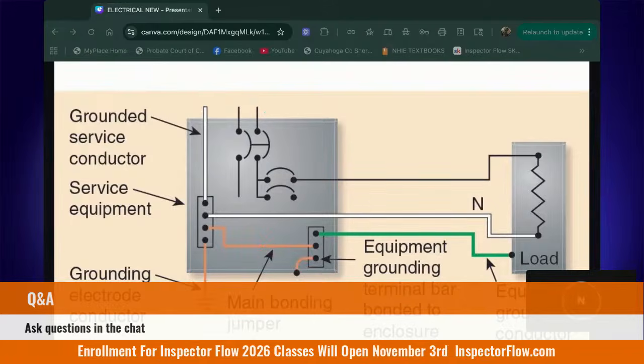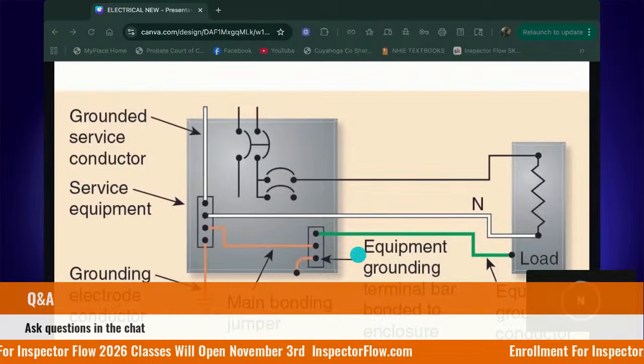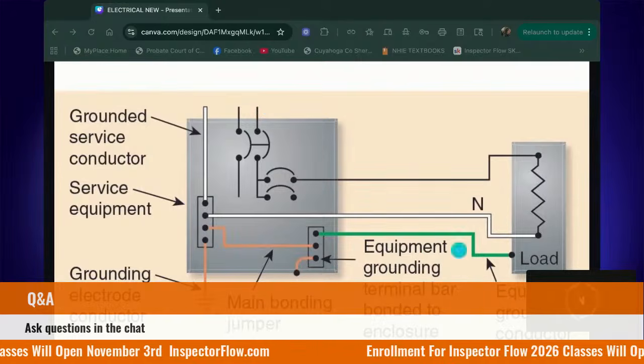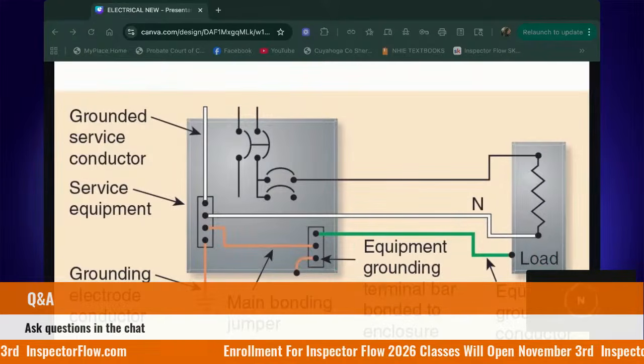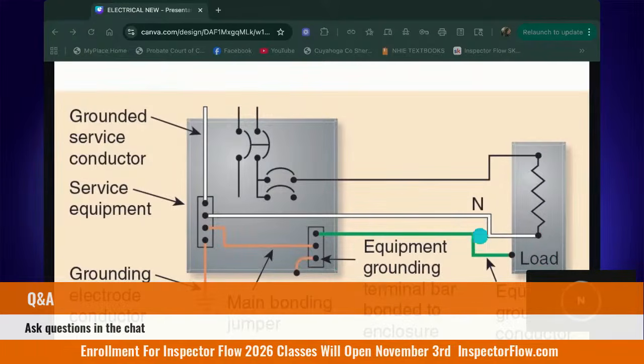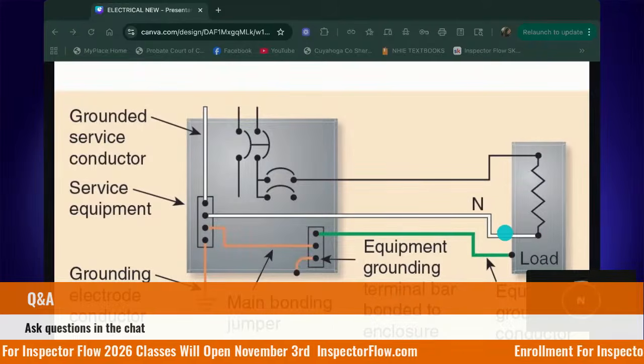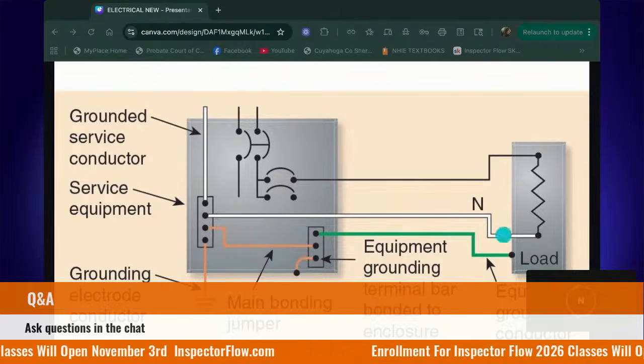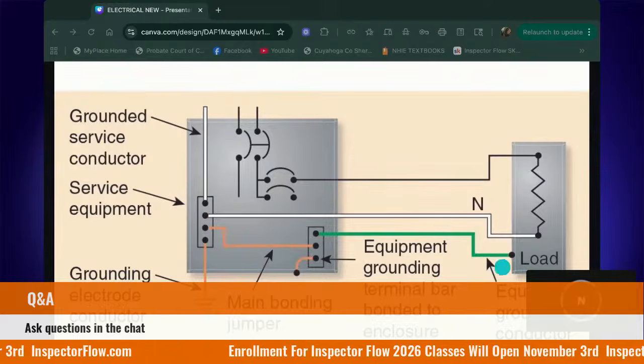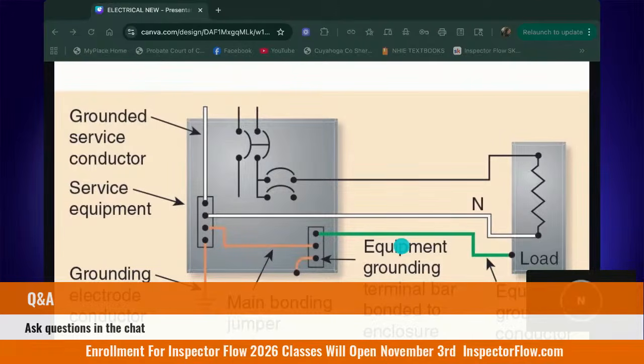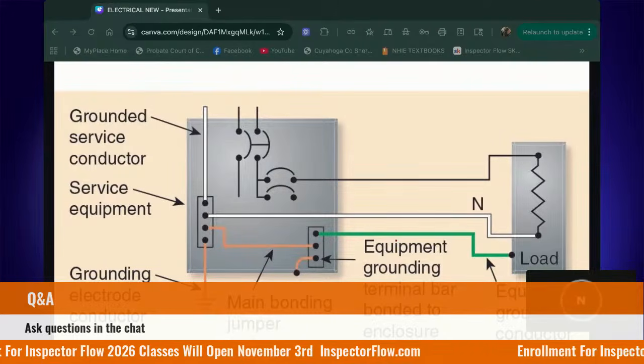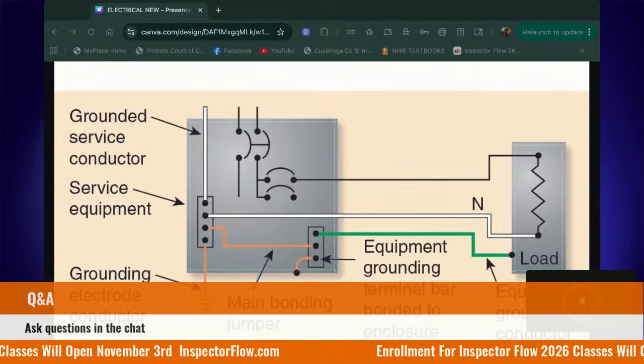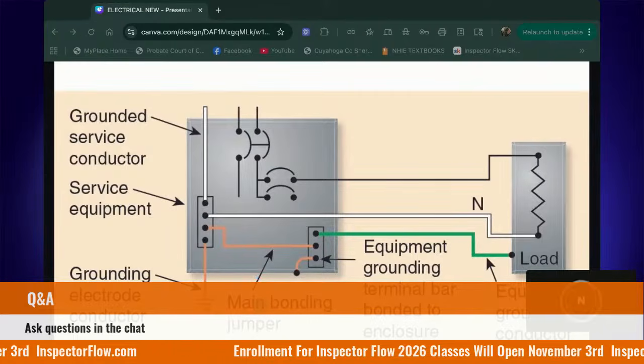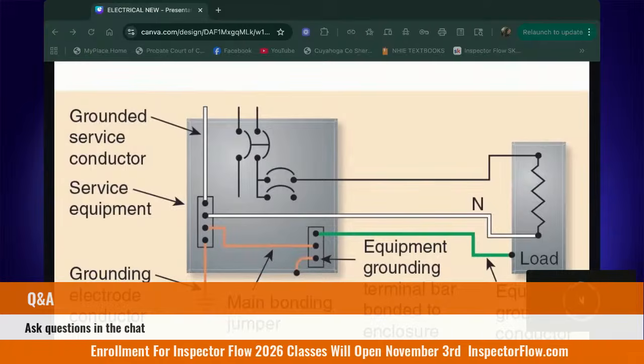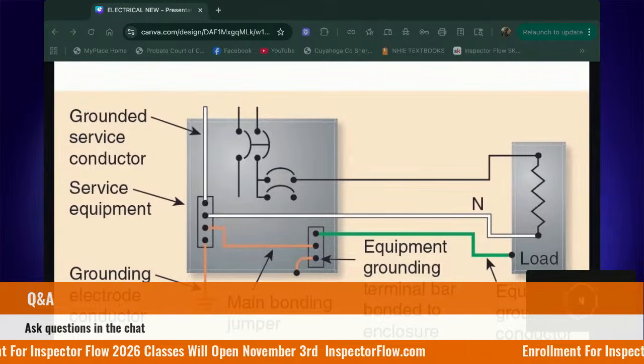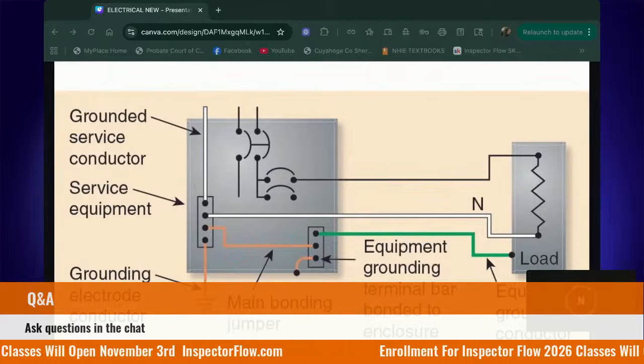Not under normal conditions. That's correct, because this is safe. This is safety only. This is my pressure release valve in case it's too much. This here is my normal return path. Okay? These wires, my grounding wires, are not carrying current. They're waiting for a problem. They're waiting for a fault. When that happens, the fault current will flow through these wires back to the panel.